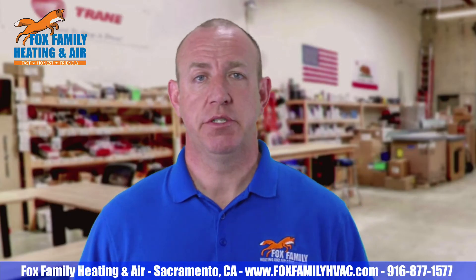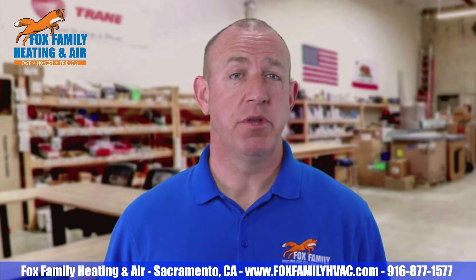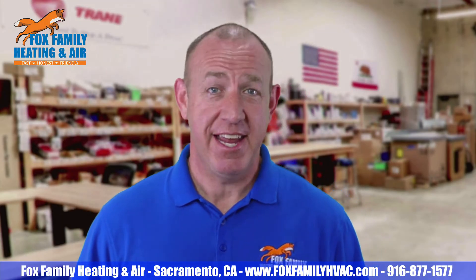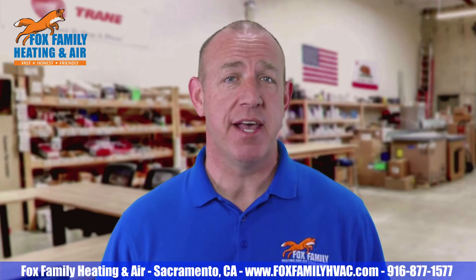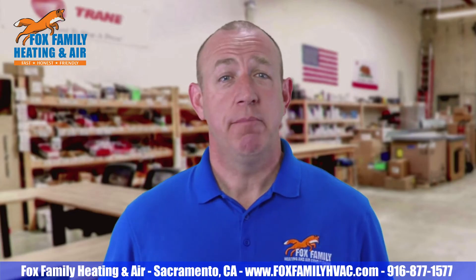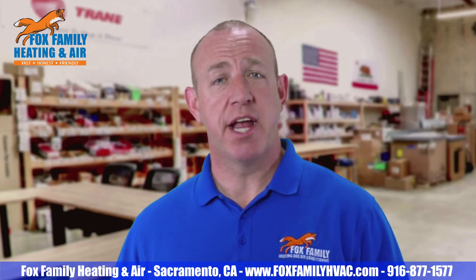So what are some of the solutions? The obvious solution is buying a ventilating dehumidifier. Whether the AC is operating or not, running a dehumidifier is great for when the AC cools the house fine but doesn't reduce the humidity enough. Energy recovery ventilators (ERVs), heat recovery ventilators (HRVs), and whole house fans actually bring in humidity from the outdoors. Running bathroom fans or laundry fans is a common thought to remove moisture, but some say these fans bring in outside air which carries humidity with it.